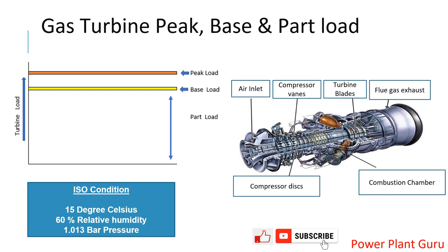The atmospheric pressure under ISO conditions is 1.013 bar. At these site conditions, if you operate your machine at full load with IGV fully open, whatever megawatt you get is the full load, meaning the base load condition for that particular machine. This is what we call the ISO standard condition at which gas turbine load is defined.